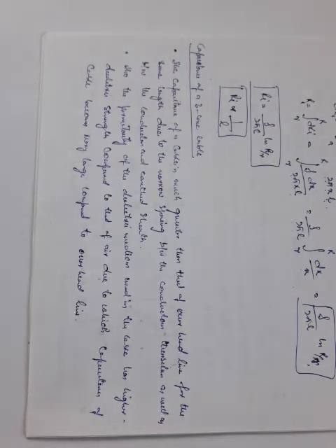Since the conductors of the cables are very close to each other, and also the sheath, which is at earth potential, is also close to the conductors. And the third reason is that the dielectric that we have used has a permittivity higher than that of the air. These three reasons will make the capacitance of the cable more as compared to overhead lines.